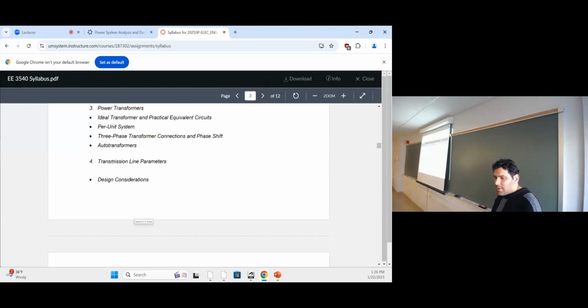Then we'll get into the big structure, which is three-phase transformers. There are single-phase and three-phase transformers. Three-phase ones are large transformers with three independent transformers connected together, but their issue is they have really complex connections and a phase shift problem. When you get from the primary to the secondary side, you're not just transforming the voltage value, you're also affecting the angle, because voltage is a phasor with magnitude and angle. So there'll be some phase shift when making voltage transformations over those three-phase transformers, and it's very important. We'll get into those calculations.